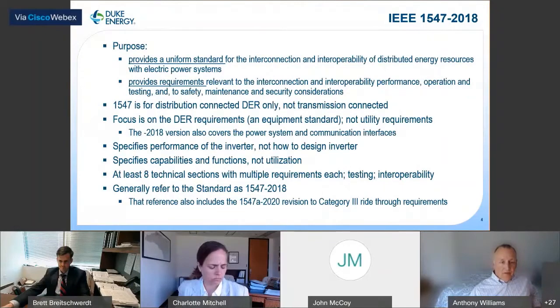So very quickly on the purpose of the standard, there's two main parts I wanted to talk about: the uniform standard piece, and then also the requirements. In terms of a standard, it's for interconnection, it's not just about the capacity, but also about uniformity across the DER equipment itself. So just making it a more standard device and easier to understand what's there. The interoperability piece, a little bit of a strange word to me, but I think of it just in terms of SCADA. So that's the control and the data that's shared between the utility and the DER.